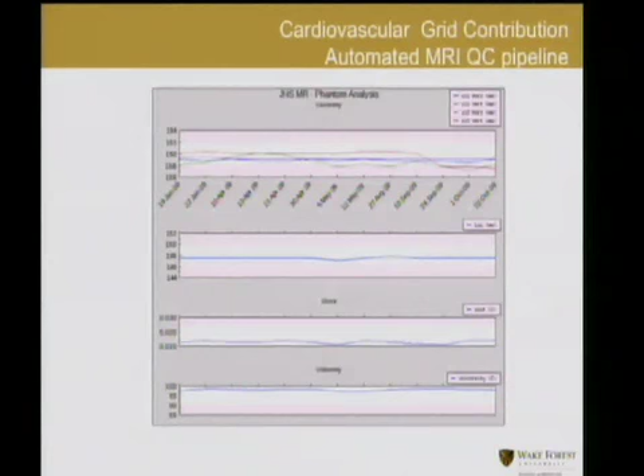And so, working with Ray Winslow at Hopkins, who's the lead of the Cardiovascular Research Grid, we envision a project in the Cardiovascular Research Grid to develop this as a pipeline that anybody in the world could upload their phantom images from their MR scanner to, and it would be benchmarked against the database of other MR scanners. So you'd know if you have a Siemens 1.5 Tesla, is it performing the same or different from everybody else?